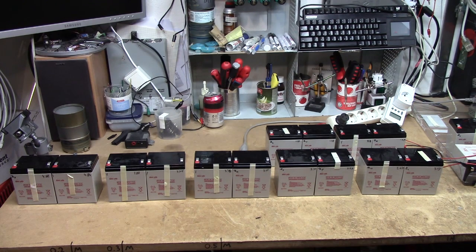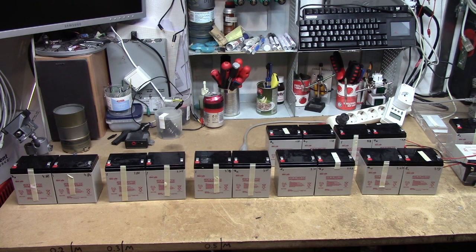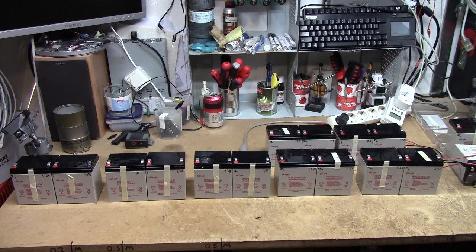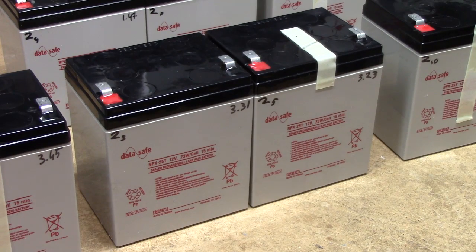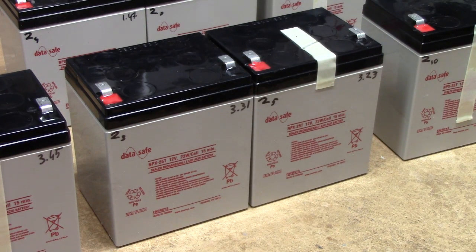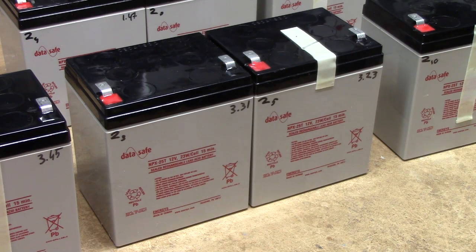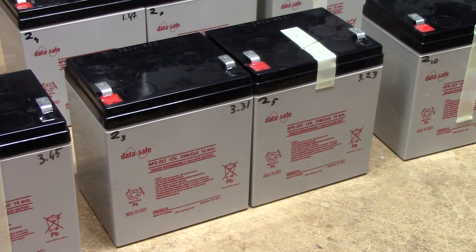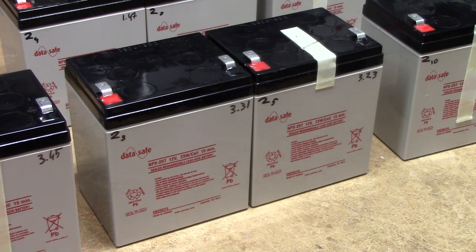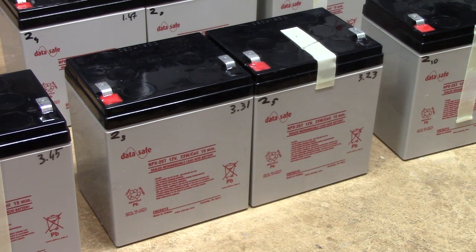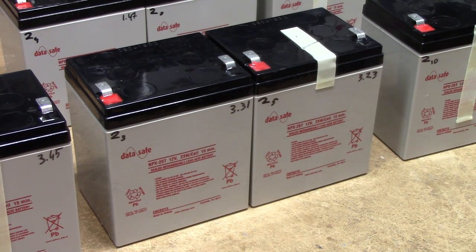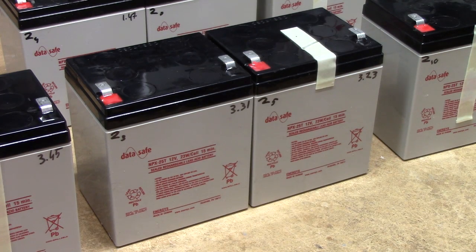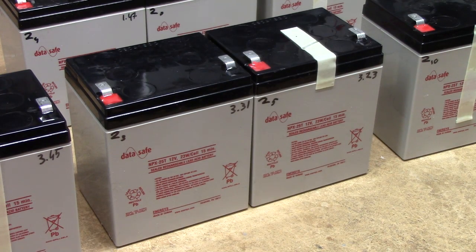I'm just going to hook these batteries up starting with group number one over there to the left and let them soak for a maximum of one week. The batteries in question are EnerSys datasafe batteries which are relatively high grade sealed AGM batteries which are specified to be 5 amp hours at a 20 hour rate or at 1 amp they should last between 30 and 40 minutes when new.